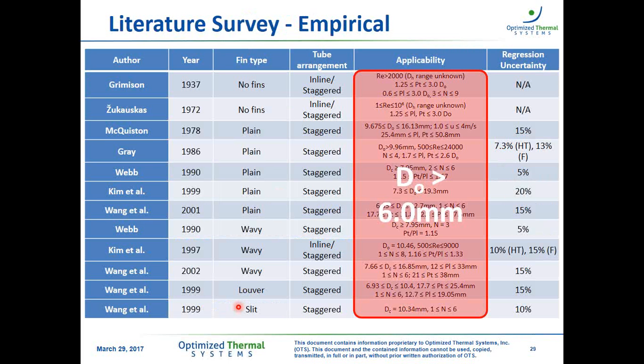If you look at the applicability, none of them were actually developed for tube diameters above 6 millimeters. And why is that important? Because correlations, as I said, are mere mathematical functions that correlate two sets of data, and we have absolutely no confidence that extrapolating a correlation can give us a confident prediction if we're using a small diameter tube, for example, or if we extrapolate any of the design parameters to which the correlation was not developed for.